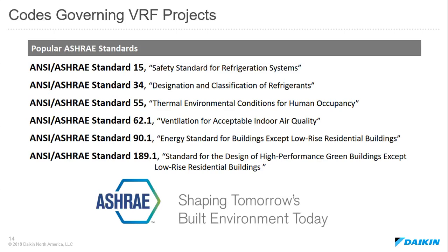Other codes that are very popular and used quite a bit in our industry are the ASHRAE Standard 55, which is thermal environmental conditions for human occupancy, ASHRAE Standard 62, which is the ventilation acceptable for indoor air quality, and ASHRAE 90.1, which is the industry standard for buildings except for low-rise residential buildings. ASHRAE 90.1 actually governs a lot of the efficiency standards that are used for the acceptance of VRF. And then there's also the standard for the design of high-performance green buildings, which is ASHRAE Standard 189.1.